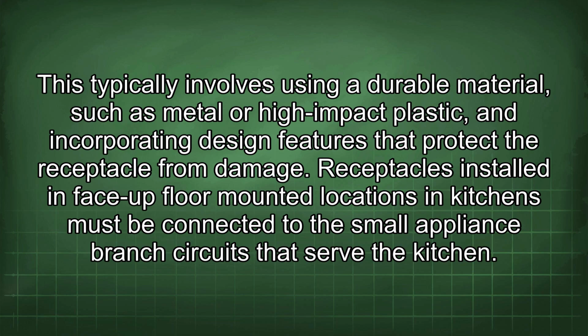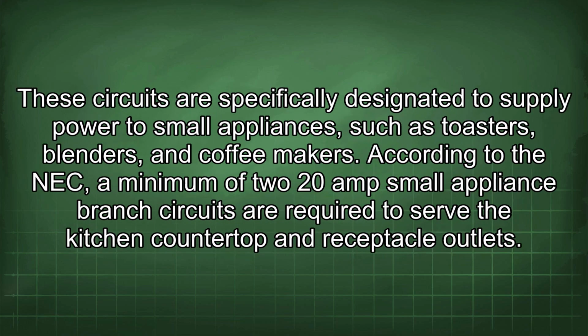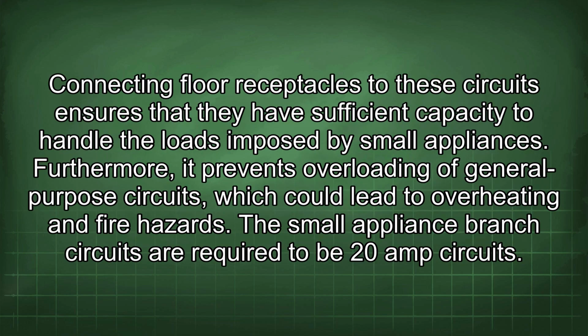Receptacles installed in face-up floor-mounted locations in kitchens must be connected to the small appliance branch circuits that serve the kitchen. These circuits are specifically designated to supply power to small appliances such as toasters, blenders, and coffee makers. According to the NEC, a minimum of two 20-amp small appliance branch circuits are required to serve the kitchen countertop and receptacle outlets. Connecting floor receptacles to these circuits ensures that they have sufficient capacity to handle the loads imposed by small appliances. Furthermore, it prevents overloading of general-purpose circuits, which could lead to overheating and fire hazards.